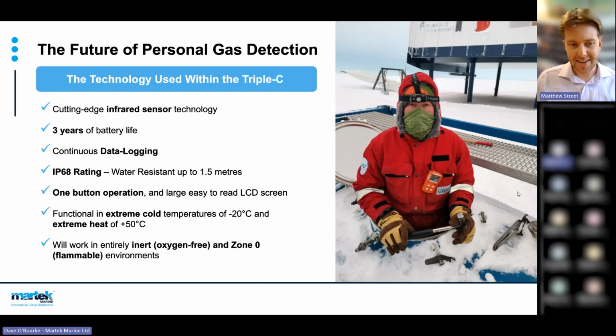And at the last point, it will also work in an inert atmosphere and in zone 0 environments, again because of the infrared sensor. There's no catalytic sensor and no combustion occurring in the device, which actually separates the CCC from the vast majority of personal gas detectors on the market, as most are only certified to zone 1 environments, whereas the CCC is good for zone 0. Essentially, anywhere on board a tanker, you don't have to worry.